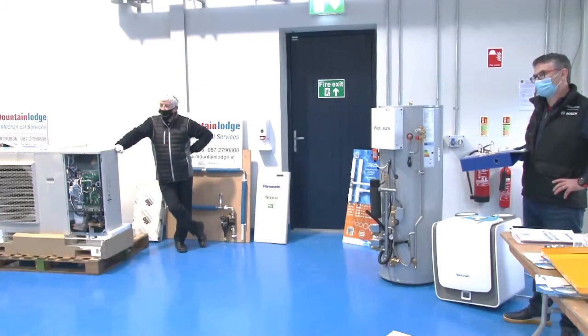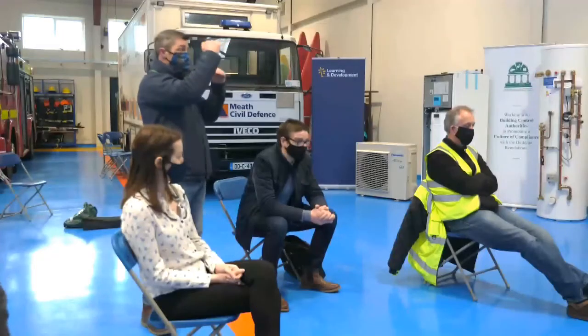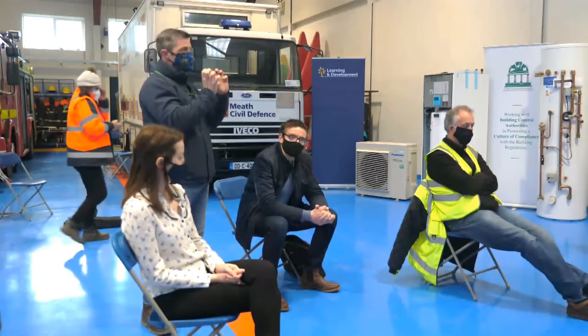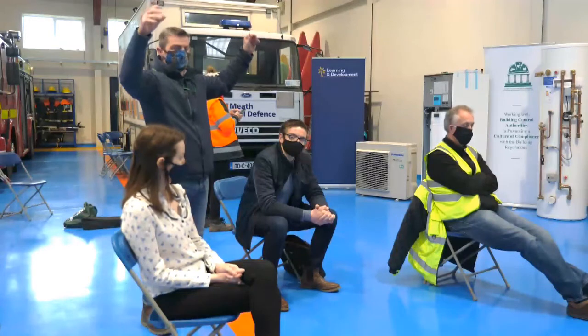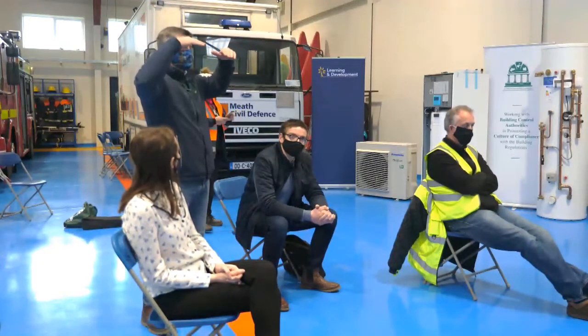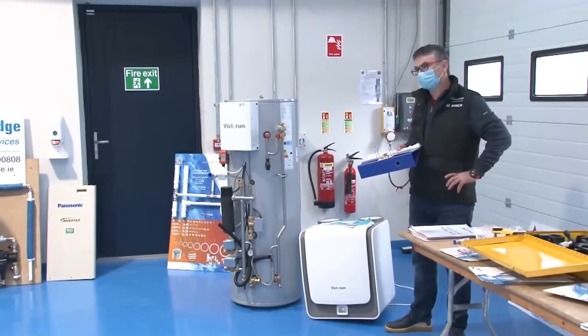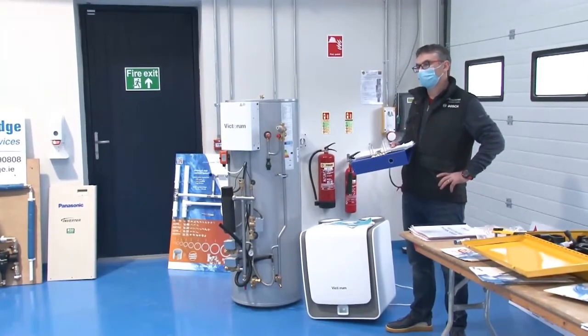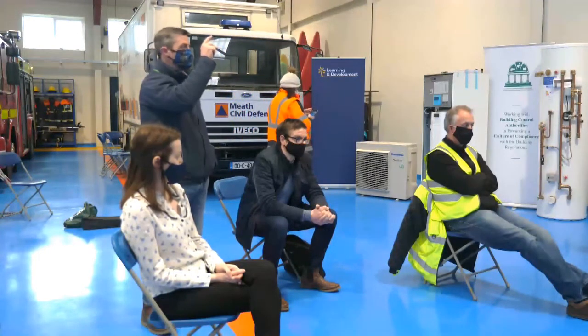Yeah, your duct where it comes down through the ceiling. Anywhere there's a false ceiling, even in a house where you have engineered joists, that's considered a suspended ceiling, so everything that penetrates through it has to have a fire collar. Especially in apartment blocks, you're going to have a concrete floor preferably that's sealed, then a false ceiling for this duct to go through, and that's all purposely from the wet rooms feeding into this here. So you're going to have to check the fire breaks all along where it penetrates.